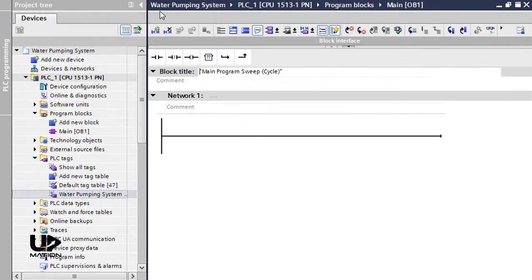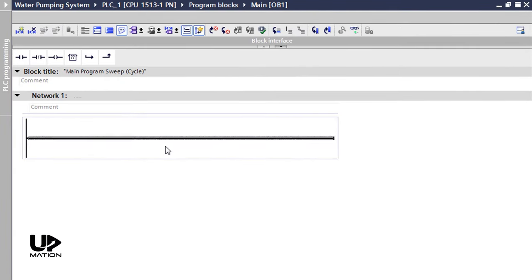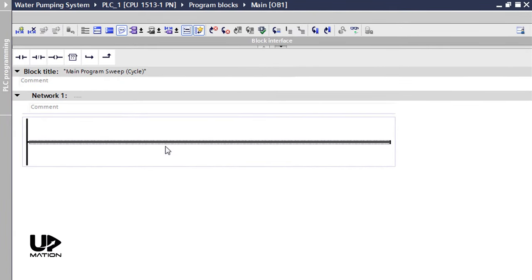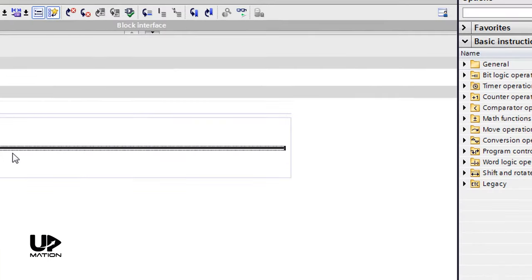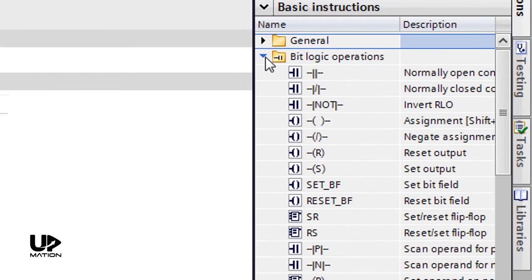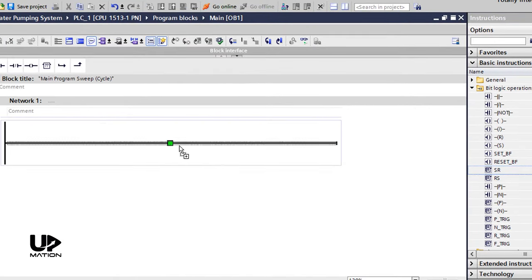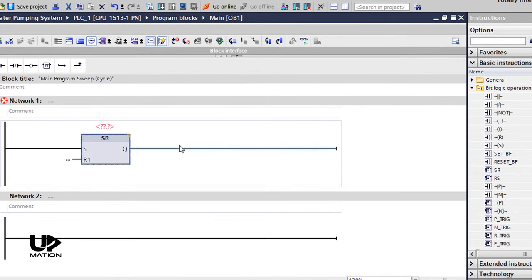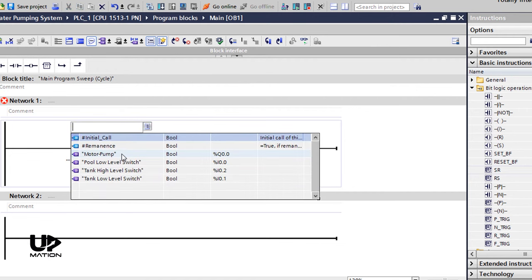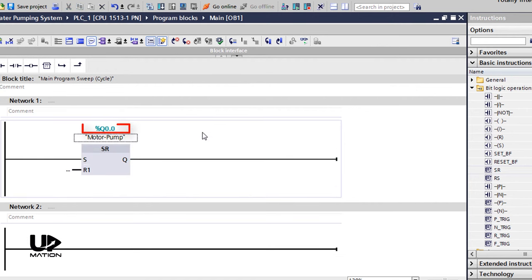Now let's get back to the OB1 environment to start our programming. The simplest way to write this program is to use a flip-flop for starting and stopping this electric motor. If you have any alternative ideas, please share them in the comments. I will expand the BitLogic Operations folder and add an SR flip-flop from there by dragging and dropping it to Network1. I then double-click over these question marks and will assign the Motor-Pump or Q0.0 to that.